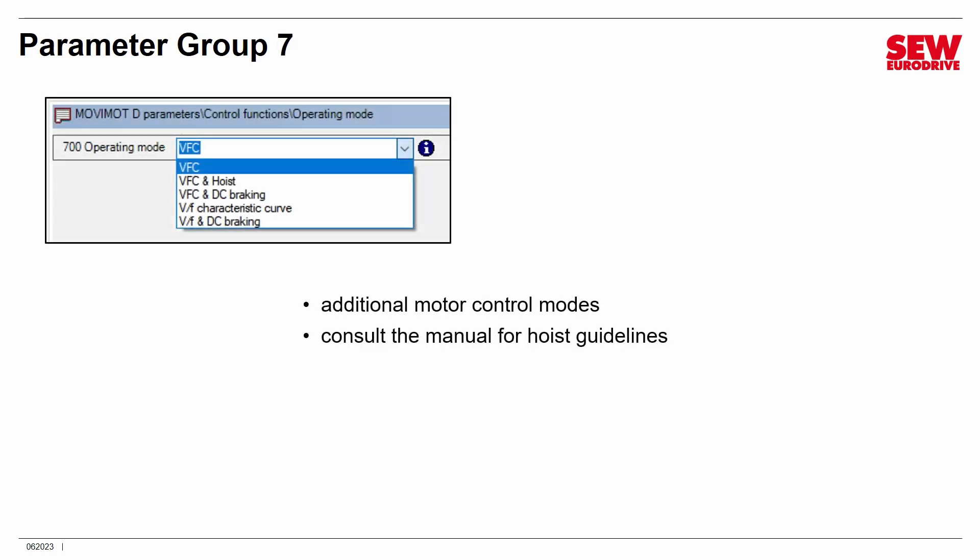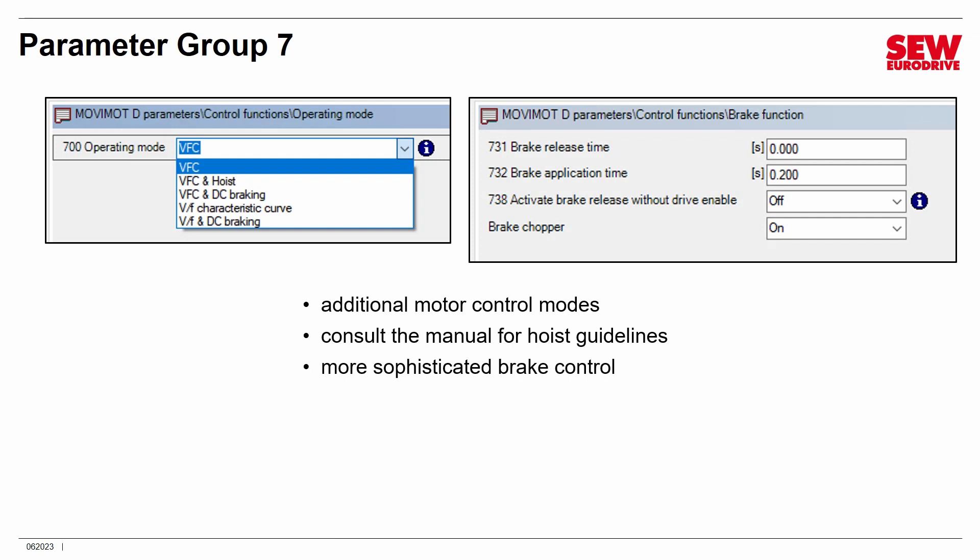Parameter Group 7 has additional motor control modes. Instead of just VF and VFC, there are now two VF modes and three VFCs. There is a VFC mode that can be used with hoists and vertical applications — refer to the manual for that as it requires very careful setup for safety. We also have more sophisticated brake control where you can set the times, and you can activate the feature where the brake can release without a drive enable — this has a parameter here in Expert Mode with the 'I' symbol.